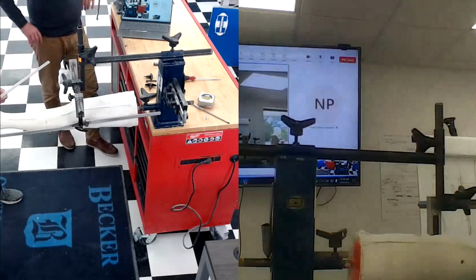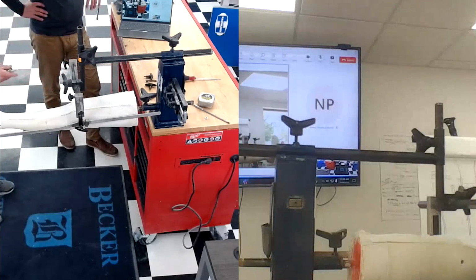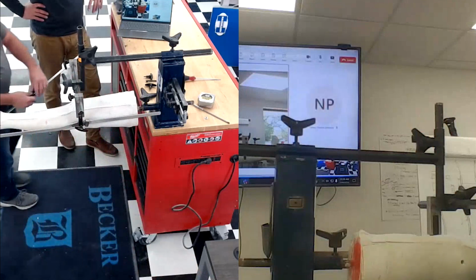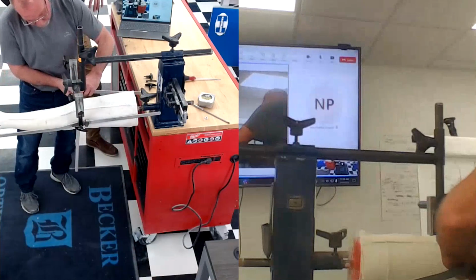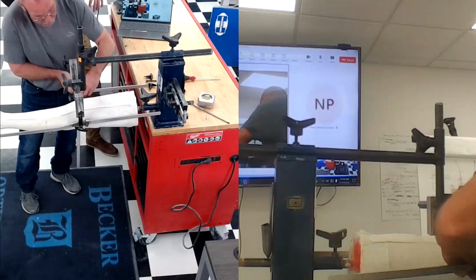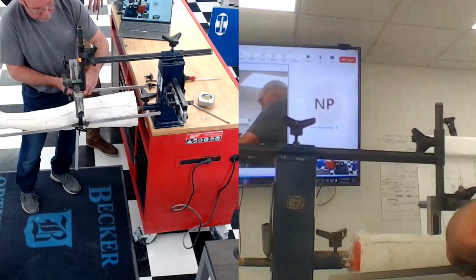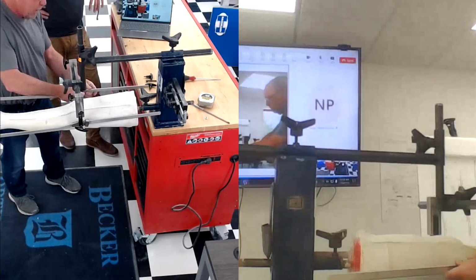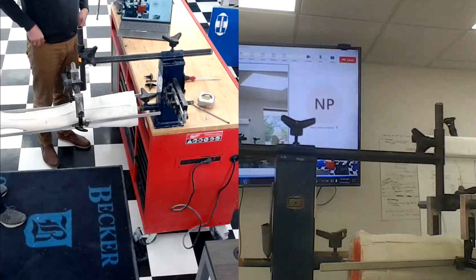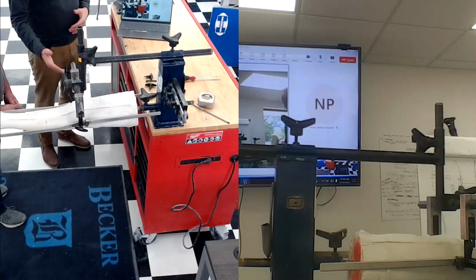Since we have a view of this medial side and the lateral side on the other camera, going to give you both there. This mold doesn't have a lot of flexion in it, but we're going to talk a little bit about how to deal with flexion too in the alignment position. There are periods in time when the mold is in flexion, but they don't want the flexion in there. And there's also times when obviously the flexion exists and is necessary. So you have to know what the fabrication instructions are and whether we're going to accommodate that flexion or build it out of the mold. Without doing a cast correction, you can correct it in the bending process.